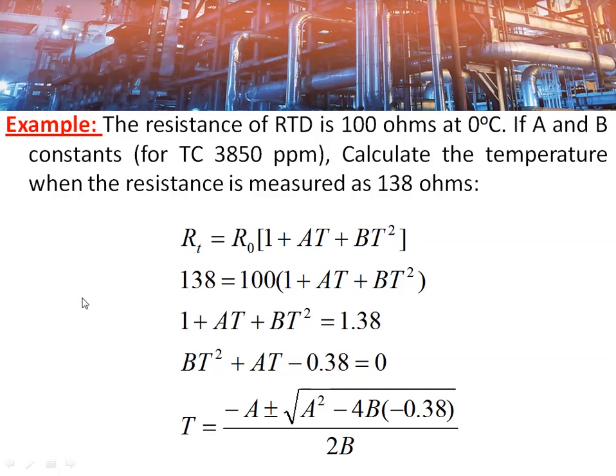Here is an example showing the use of the Callendar-Van Dusen equation for getting the temperature-resistance relationship. The resistance of the RTD is 100 ohms at 0°C. Using the constants A and B for a temperature coefficient of resistance of 3850 ppm, we need to calculate the temperature when the resistance is showing 138 ohms. This 138 ohms is measured by the signal conditioning circuit and must be converted to temperature. Using the equation: 138 = 100 × (1 + AT + BT²), we get the quadratic equation: BT² + AT − 0.38 = 0.